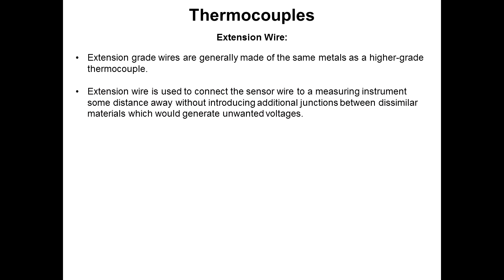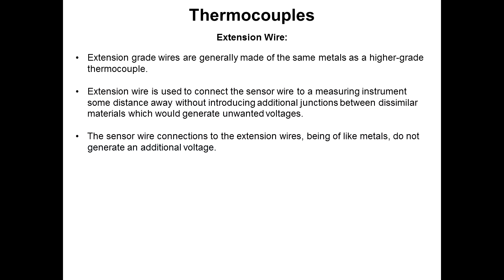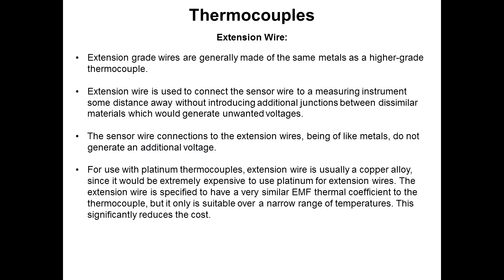If you have to run some distance away, you would not want to use a different material, which would generate an unwanted voltage where the junction is connected. The sensor wires, being of like metals, do not generate an additional voltage, so they're good for that. For platinum thermocouples, which are usually used for very high temperatures, extension wire is usually a copper alloy since it's extremely expensive to use platinum wire for these extension wires. The extension wire is specified to have a very similar EMF thermal coefficient to the thermocouple, but is only suitable over a narrow range of temperatures. But this will significantly lower the cost of this application.